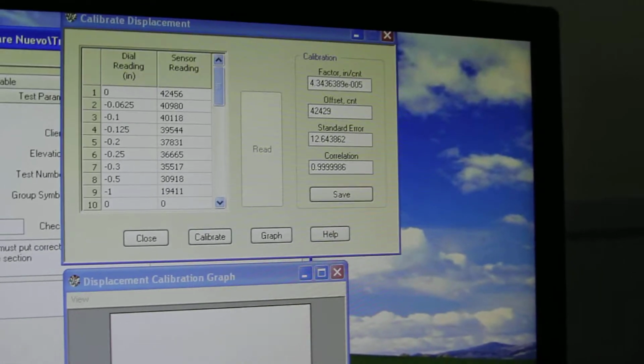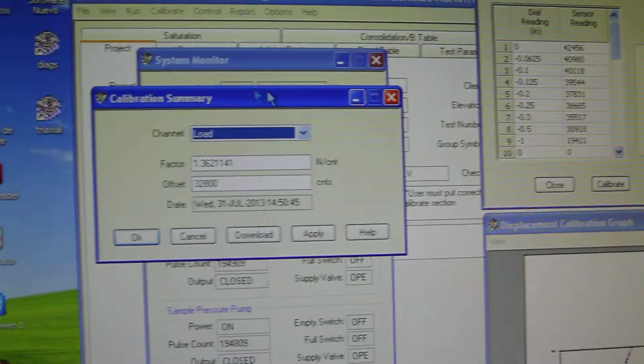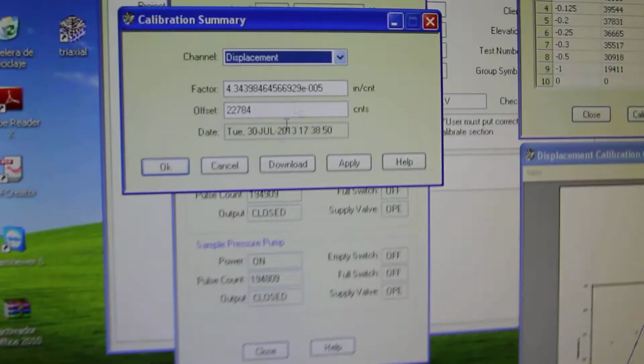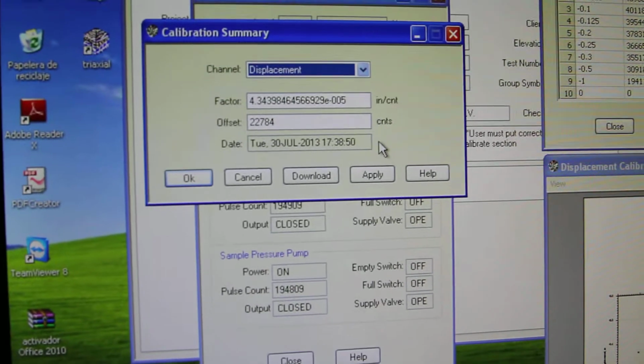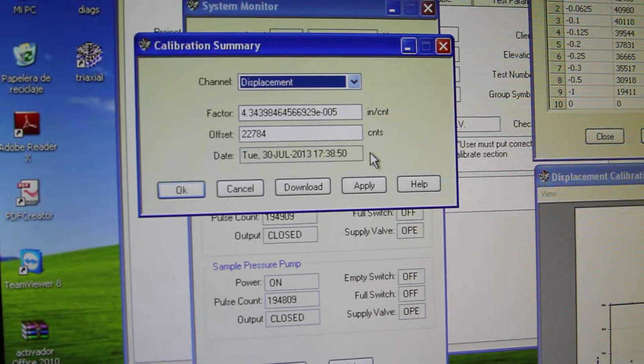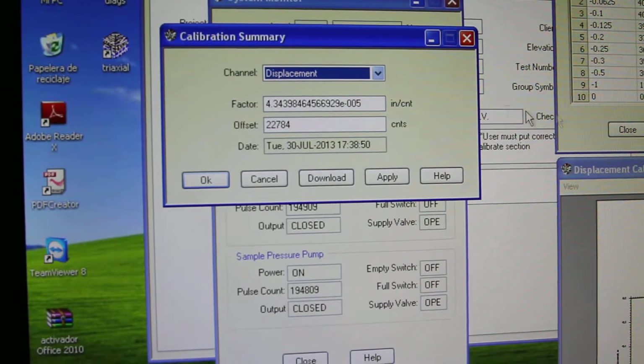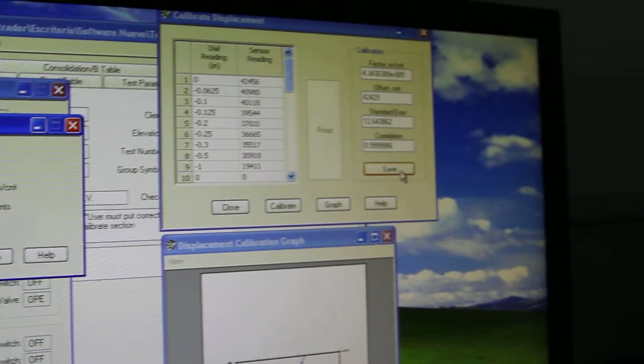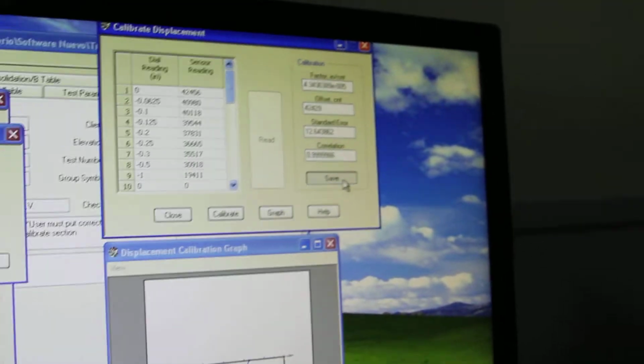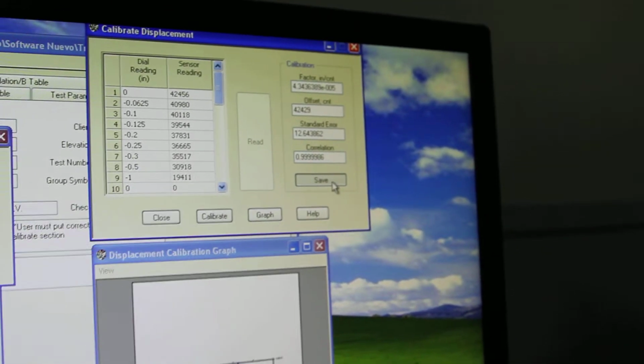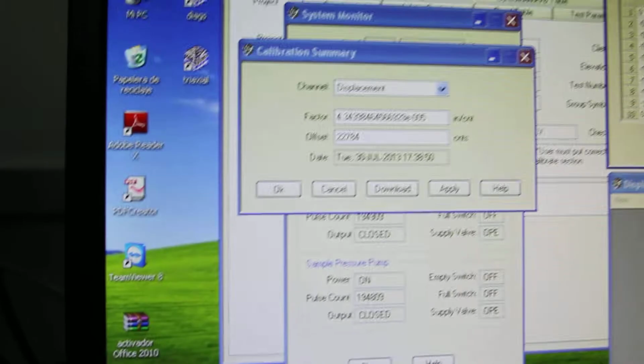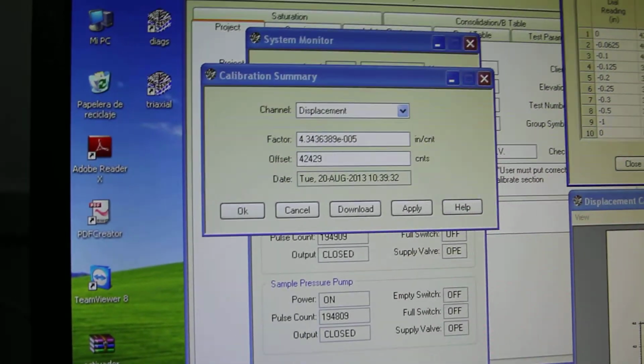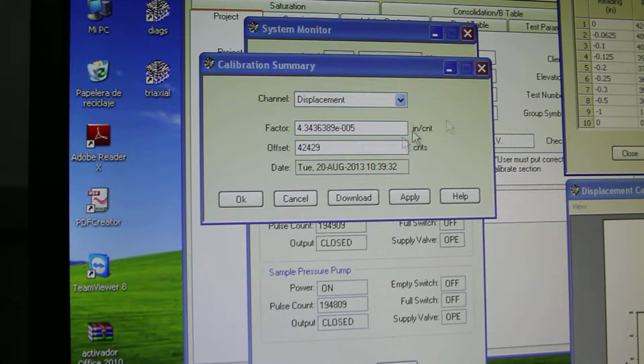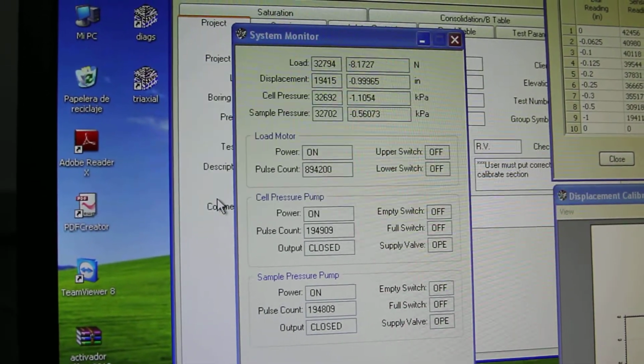When I look at my summary here on my displacement, this is the old one that was done on July 30th. And this is the calibration factor. When I hit save in my calibrate displacement menu, the software will automatically take this factor and this offset, put them in here and update the date when it was done. So this is our new calibration, and you do apply and you do OK, and we're done with the calibration of the displacement sensor.